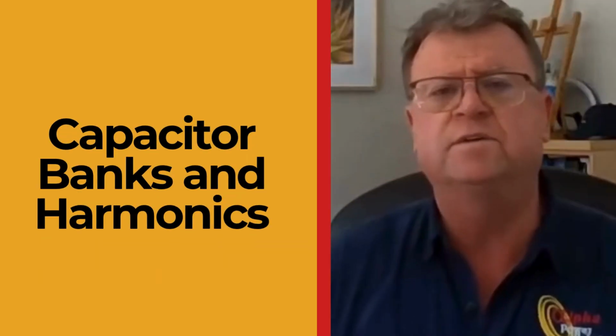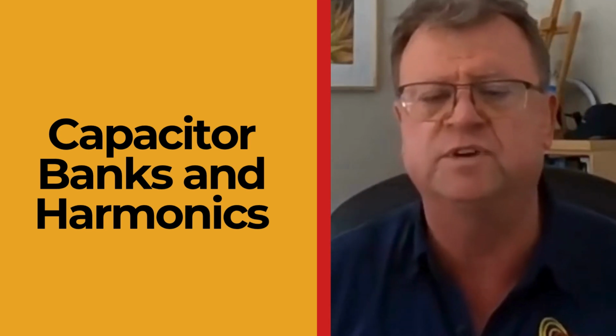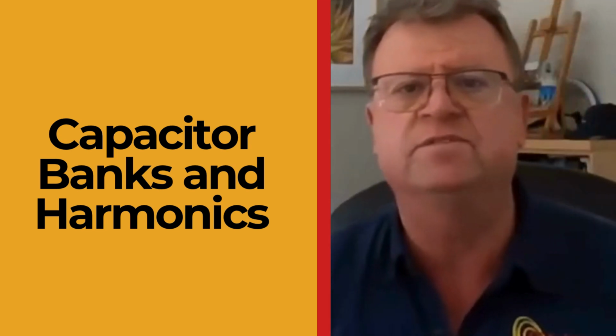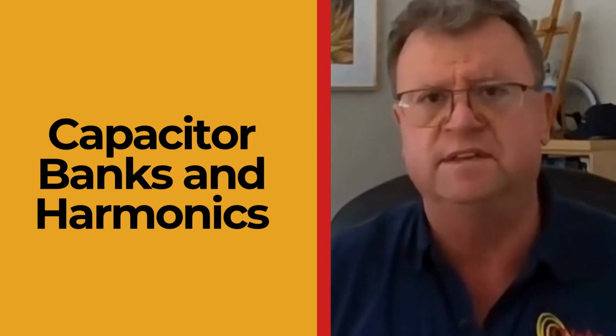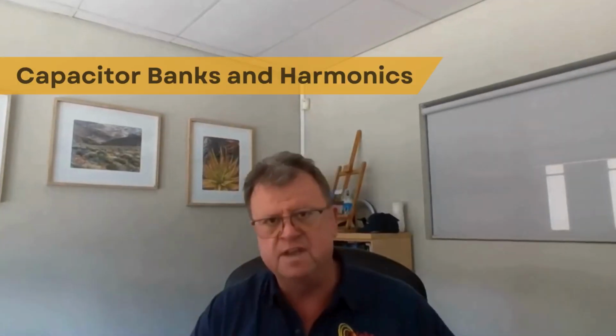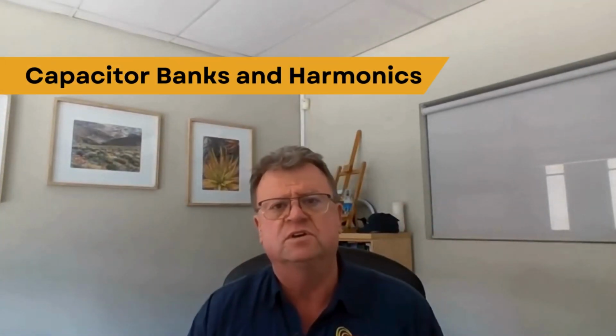And then you will have all the information that you need to be able to come up with the optimal solution. So standard capacitor banks, and by that I mean capacitor banks that don't have harmonic blocking reactors fitted to each of their steps, if they're installed in an environment where the harmonics are elevated, the capacitors will attract these harmonics towards them and amplify them and raise the harmonic content of the site quite significantly. So this worsens the situation and may increase the harmonic levels to unacceptable limits.